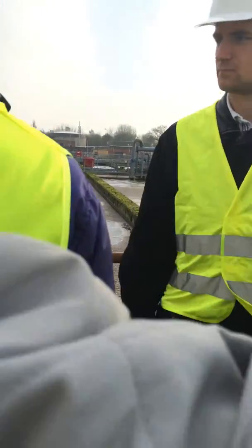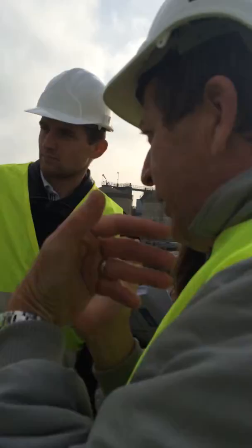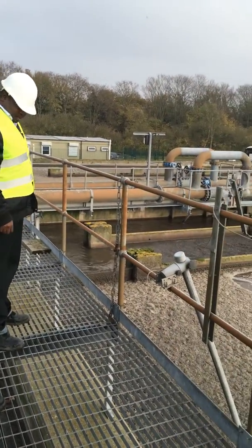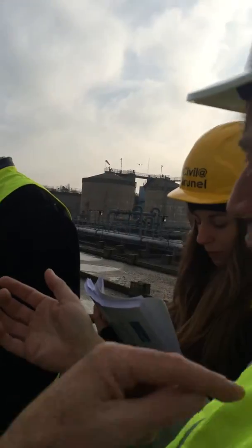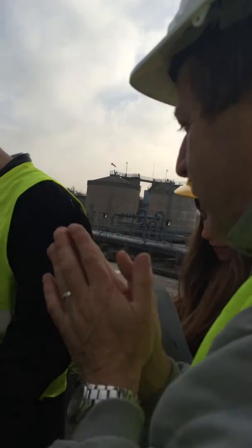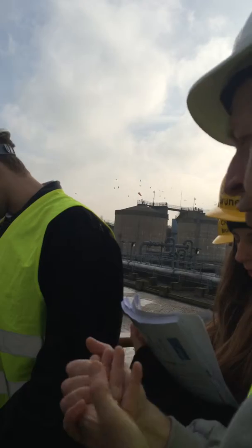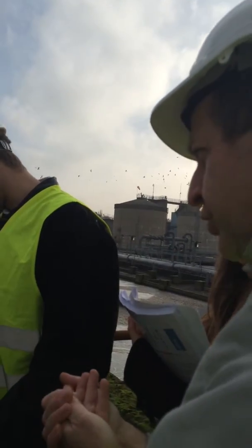So the settled sewage flow comes in, it's split into 6. A sixth of the flow comes through the head of this lane. It's mixed with the activated sludge from the end of the process, which is taken out of the clarifiers and recycled back. So we've now got this mixed liquor, we've got the biomass, which is the activated sludge, that's all the bacteria we need to do the treatment. We're adding settled sewage to it.